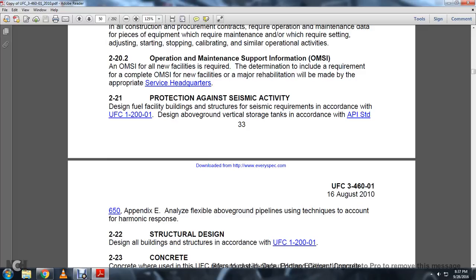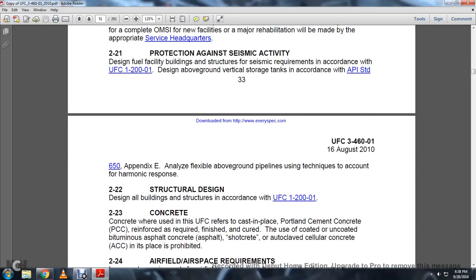221. Seismic activity. Design fuel facilities' structure and seismic requirements in accordance with UFC 1-200-01. Design above-ground vertical storage tanks in accordance with API Standard 650, Appendix E. Analyze the flexible above-ground pipelines using techniques to account for the harmonic response. 222 Structural design. Design all the building structures in accordance with UFC 1-200-01.